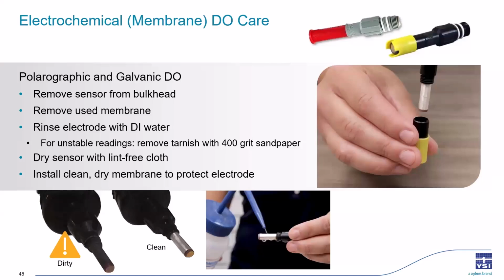Next, we have electrochemical or membrane-covered DO. To care for the sensor, remove it from the bulkhead if you need to, and remove the used membrane cap, which is that red or the yellow cap there. Then rinse the electrode with DI water. If you're having any issues calibrating or notice unstable readings, your sensor might be tarnished, and you can use a fine grit sandpaper to gently buff that anode and cathode to remove the deposits. You're not going to want to do this too often. The electrode should be buffed at most twice a year.